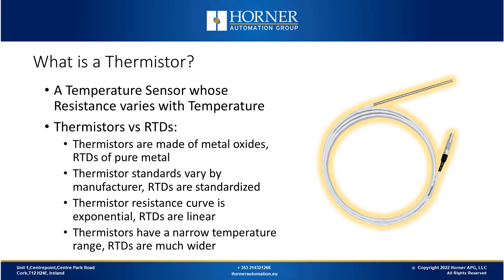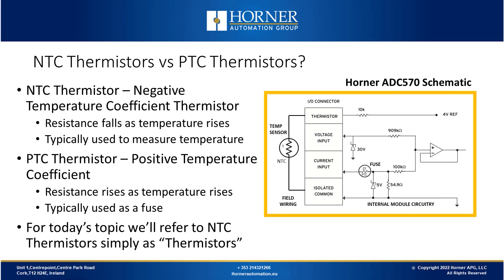Another thing about thermistors is their resistance versus temperature curve is exponential, whereas RTDs are much more linear. Also, thermistors have a much narrower temperature range than RTDs. There are two different classifications of thermistors: NTC and PTC. NTC stands for negative temperature coefficient, meaning resistance falls as temperature rises. These are the sensors typically used to measure temperature. PTC, or positive temperature coefficient, means resistance rises as temperature rises, and these are typically used as a fuse.